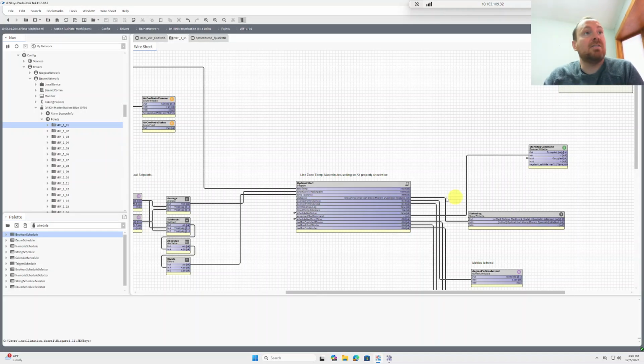This is once again a production environment, and lots of link marking: zone temp, target zone set point, temp tolerance, which is an extremely important parameter. It doesn't matter if it's metric or imperial units; if the zone temperature is within temp tolerance of set point, this block does not do anything. And then we also always need to look at the schedule's next value and next schedule start time.